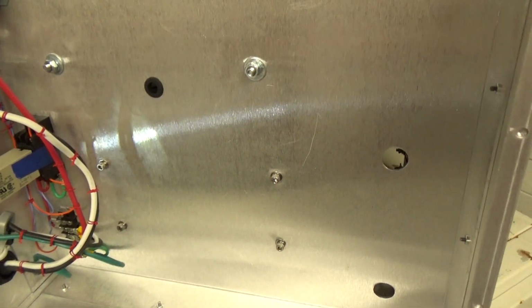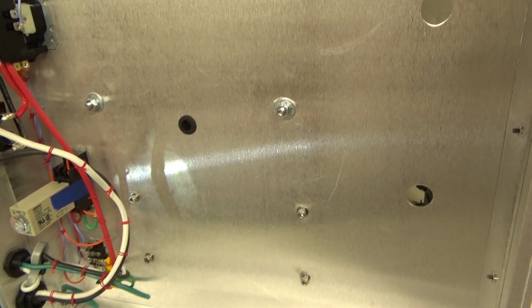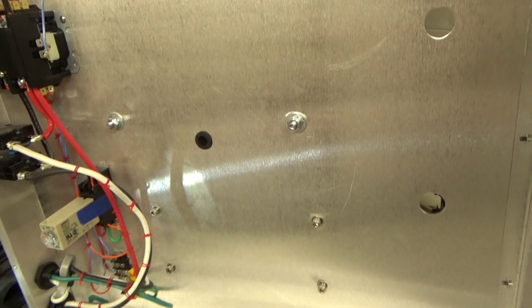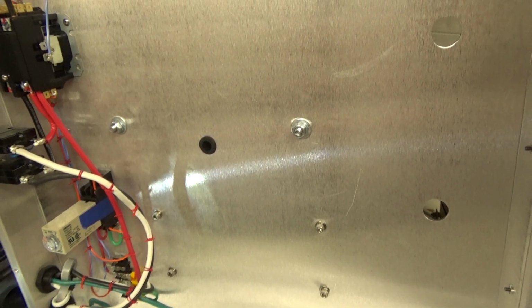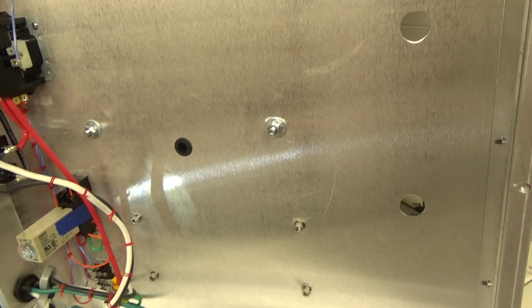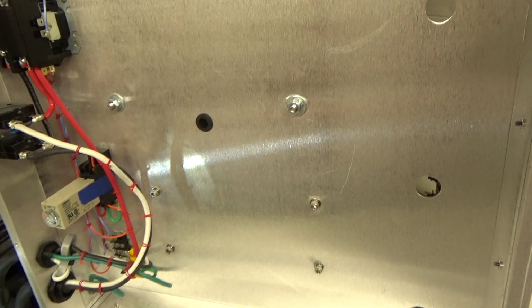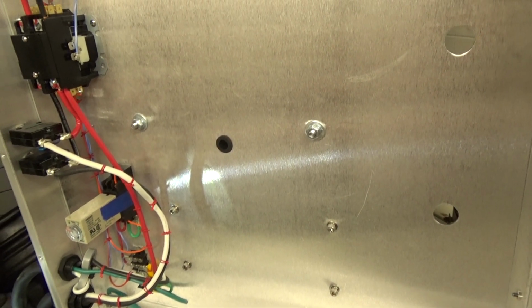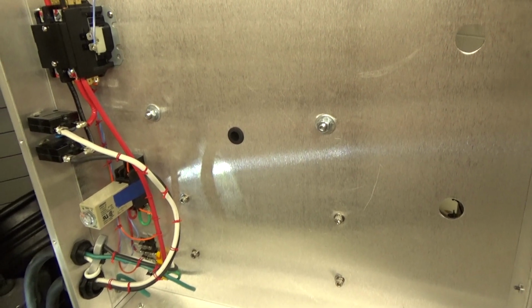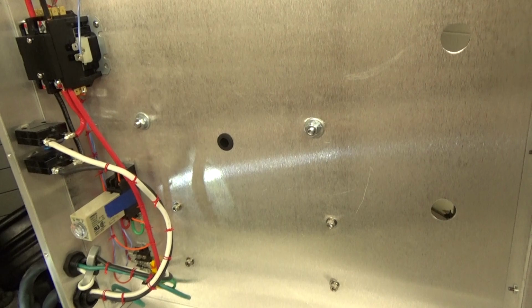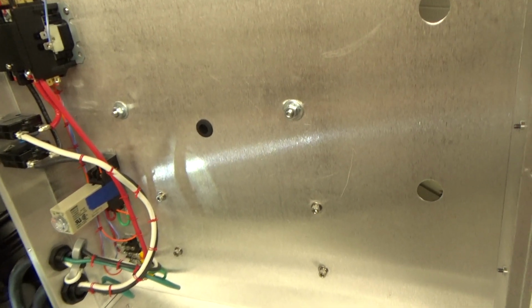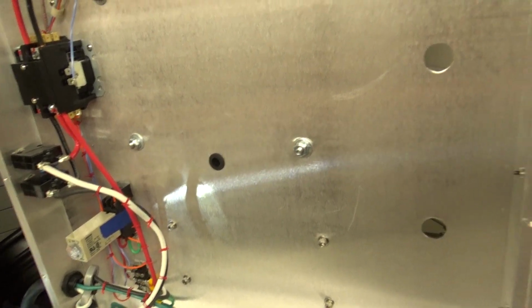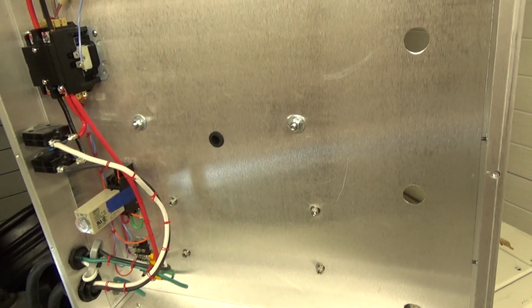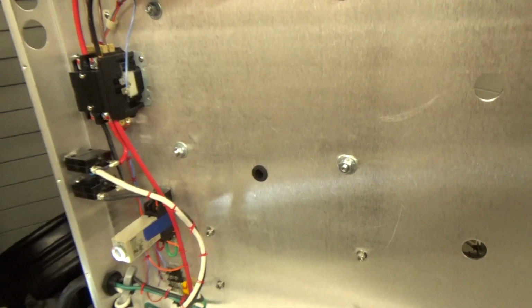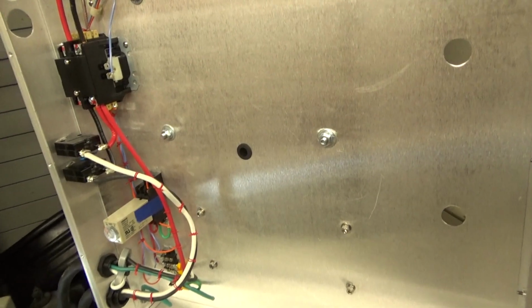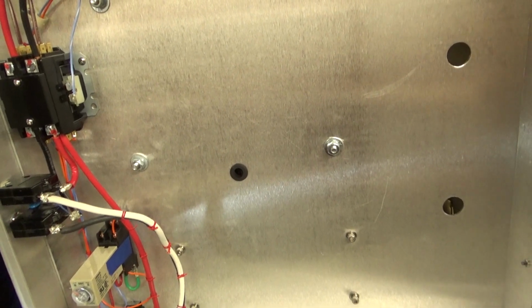So if you do the math, it's not rocket science. Just on the transformer, if you took the total kVA, take 2650 and multiply that by 1.5, that comes out to 3975. That's 3.975 kVA. If you divide the 3975 by 240, that's 16.56 amps right there. And you can pull more off. If this transformer is rated for CCS, you can pull up to 50% or so more than its total rating for intermittent periods. So, way too small.